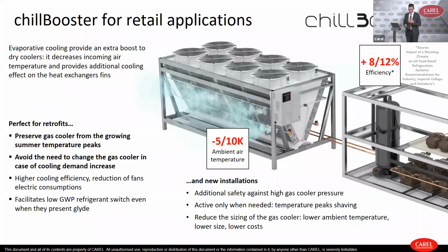Sorry again. So I was saying this is an adiabatic cooler that can be fitted on the gas cooler, and by the adiabatic effect is able to reduce the inlet temperature of the air that is coming through the gas cooler by about 5 to 10 Kelvin degrees. And at the same time, it is able to increase the efficiency of the whole unit by up to 8 to 12%, for example, by bringing the operating condition of the unit back into subcritical operating conditions.